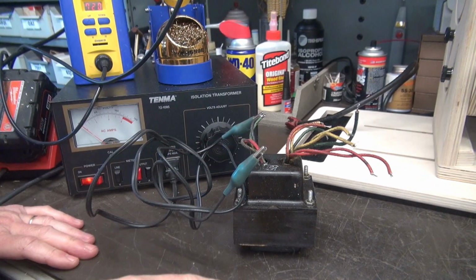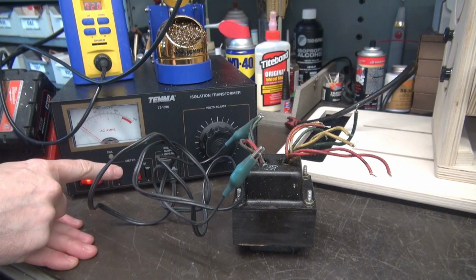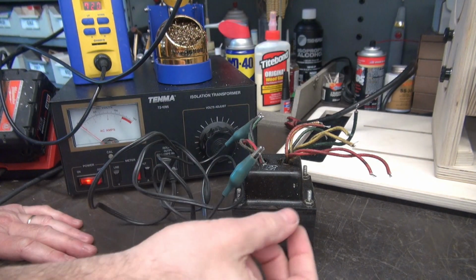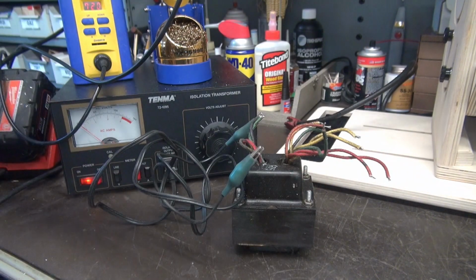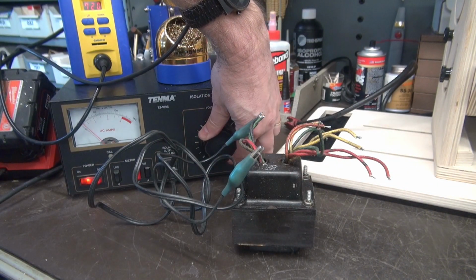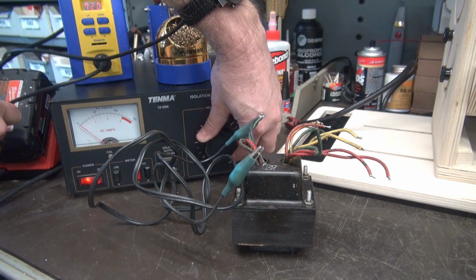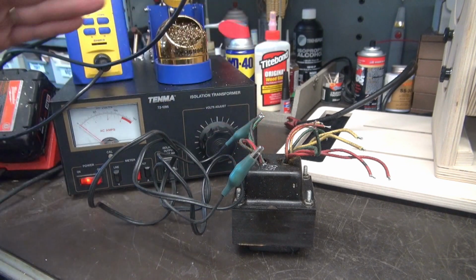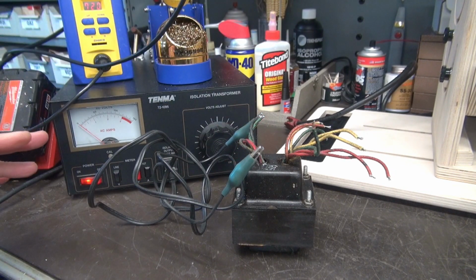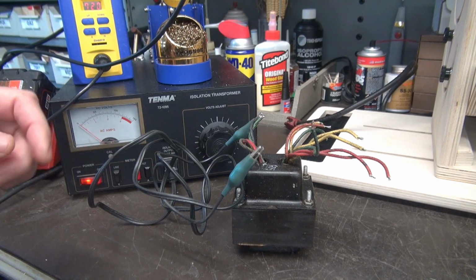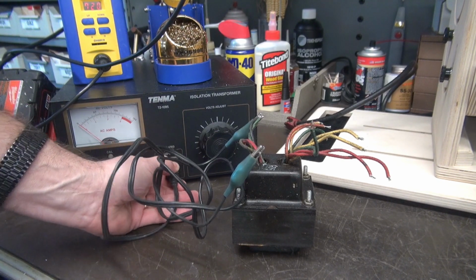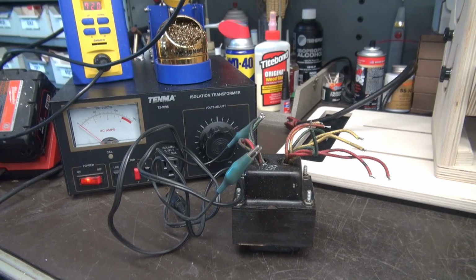So here's that power transformer hooked up direct to my variac with nothing applied to the secondaries. See that current? We still got not a short but a high current path in that transformer somewhere. So yes, it is defective. Time to change them out.